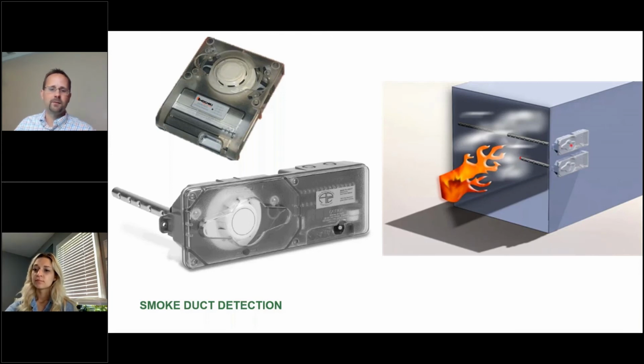And again, one size doesn't fit all. Coordinate the smoke detector type that you install with your other system needs to make sure everything operates properly. And then, who is providing the smoke detector? If you have a fire alarm system on the project, typically you want them to provide the smoke detector because it needs to coordinate and communicate with their system. If you're in a building that has no fire alarm system, then obviously it would be provided with the smoke damper, which would be easier to coordinate because it's tied in with that. So it's not a one size fits all, and you need to coordinate with the rest of the design team and the building owner when specifying these detectors.